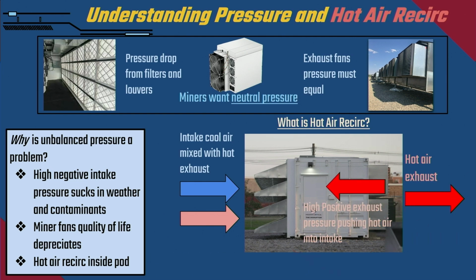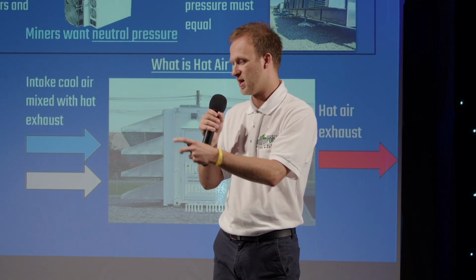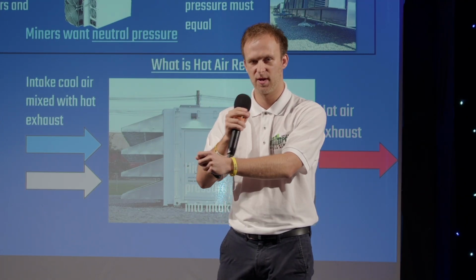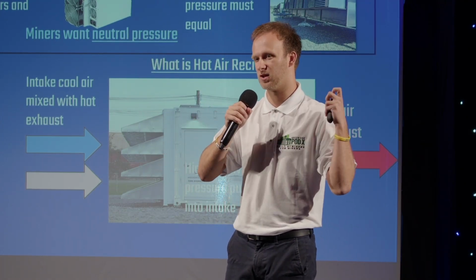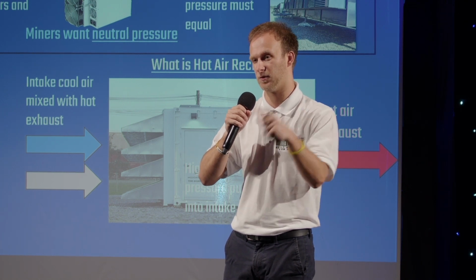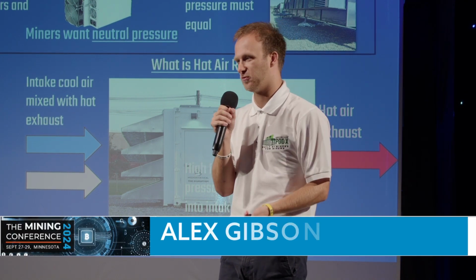Now, the opposite is also true with positive pressure in your exhaust, and that can happen if your exhaust fans aren't spec'd high enough to overcome or equal the miner exhaust fans. So if your miners are blowing out so fast and so hard that your exhaust fans can't keep up, that positive pressure builds up and it'll actually leak hot air back into your intake from the inside, which also overheats your miners.